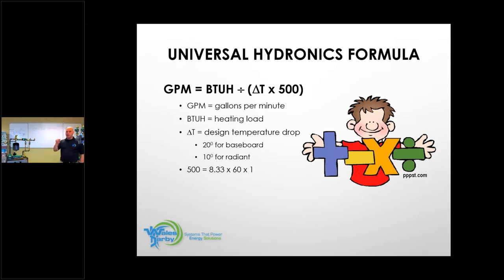And then in the formula there, you see on your screen, there's a times one. If I'm using water, it stays times one. If I'm using antifreeze, I have to look at the container of the antifreeze, and it will tell me what the rating of that antifreeze is. And I can go in and recalculate, because it will no longer be 500. It'll be lower than 500, because antifreeze wants to reject the heat. So it doesn't have the ability to absorb as much heat energy as straight water. So it will be a lower number.